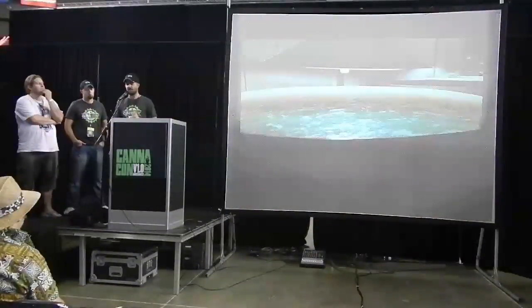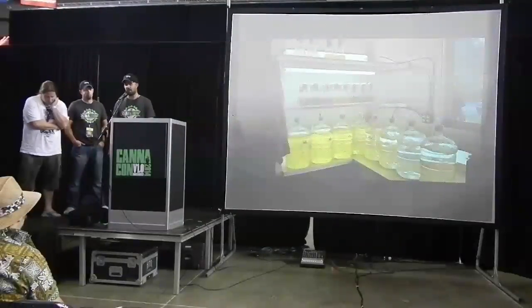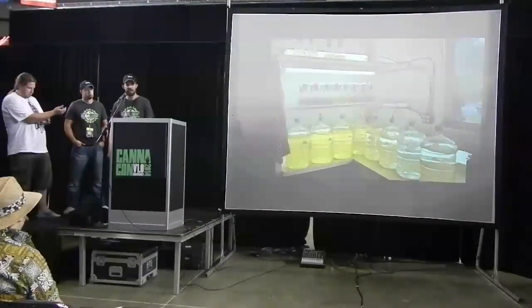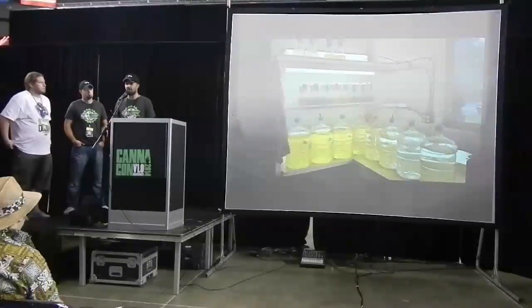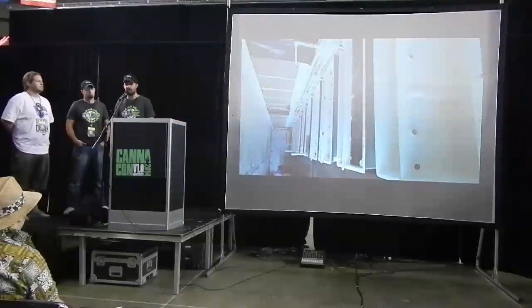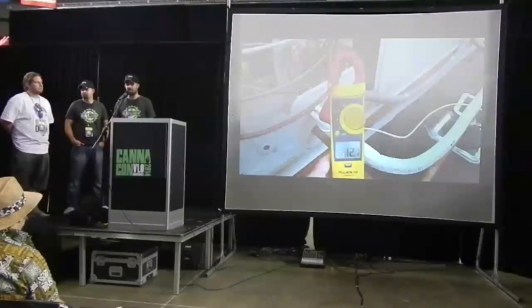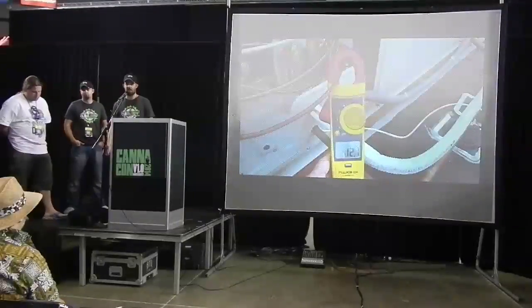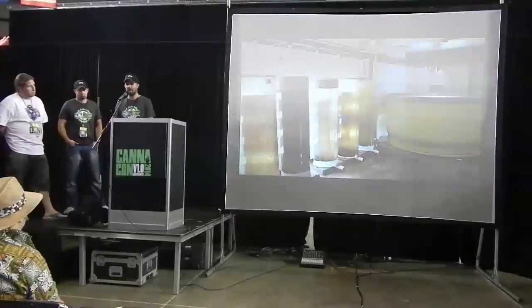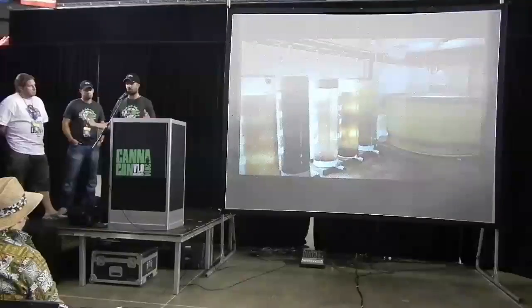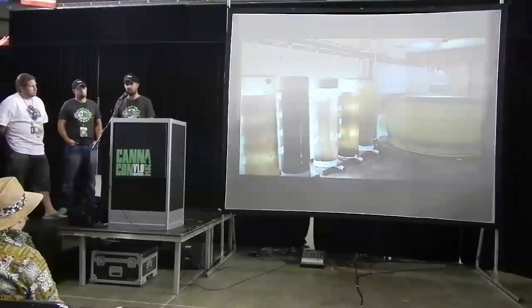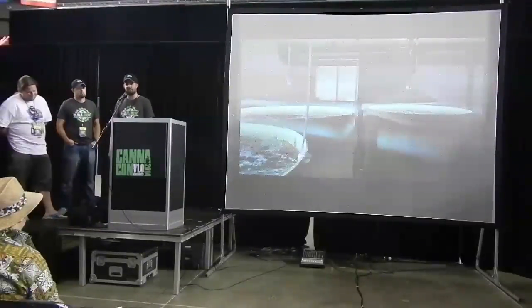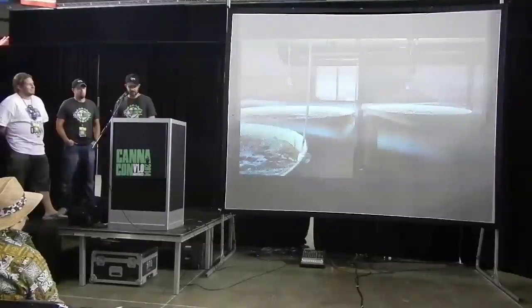We get calls all the time about that. Not necessarily the systems that we design, although we have been there in the past, but we learned our lessons. But other people who have HVAC companies come out and install these mini splits and do not take that into consideration because they're going off of square footage. The typical mini split for a home is sized off of the square footage of the house. You can have a 1-ton unit in a living room, and it can do a 10 by 20 room no problem because you don't have 130, 150 degree HID lights hanging in there. So that's a big issue.